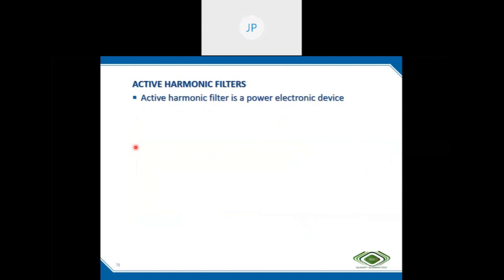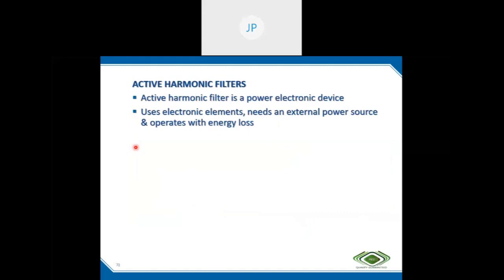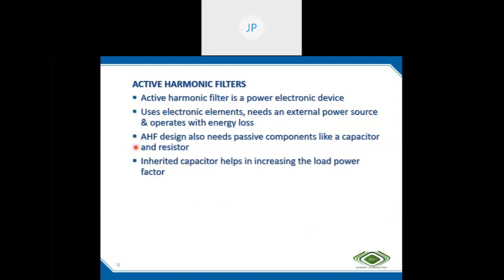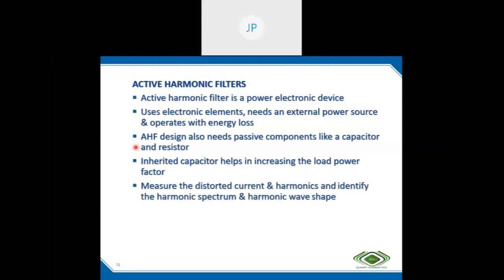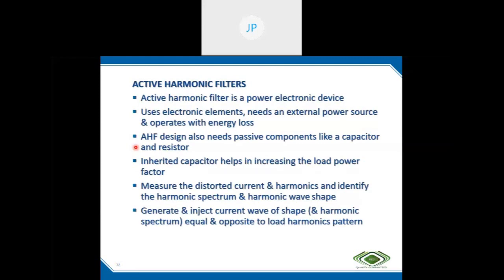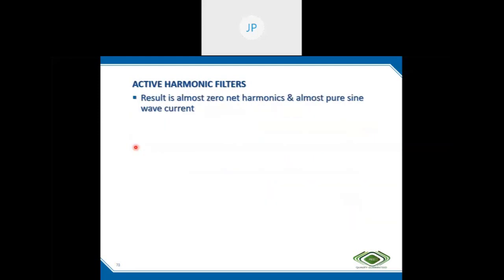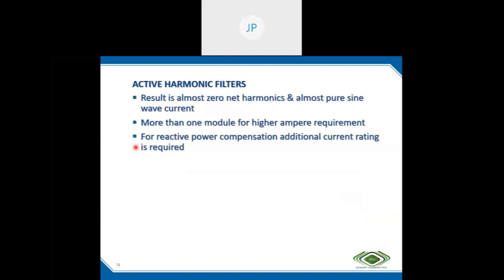Active harmonic filter is an electronic device, uses electronic elements, needs external power, and operates with energy loss. AHFs also need passive components like a capacitor and resistor. This inherent capacitor helps to increase power factor, measures distorted current and harmonics, identifies the spectrum and wave shape, generates and injects an equal and opposite one, and the net will be zero. More than one module can be used for higher ampere requirement. For reactive power compensation, additional current rating is required.